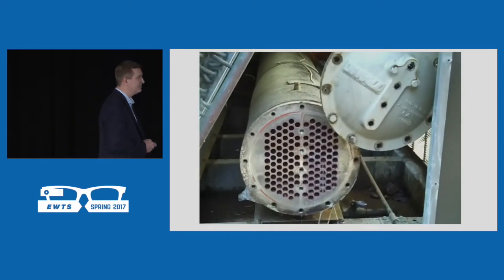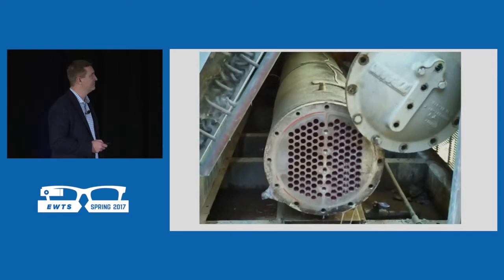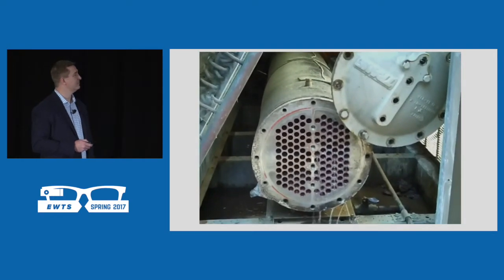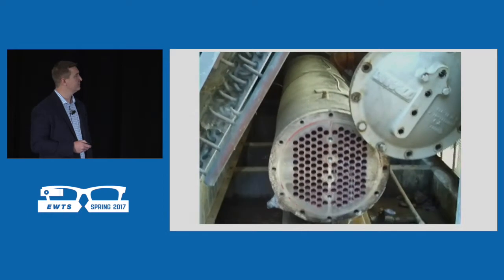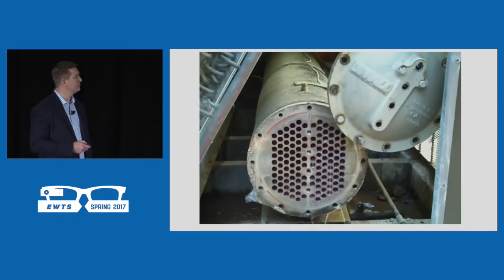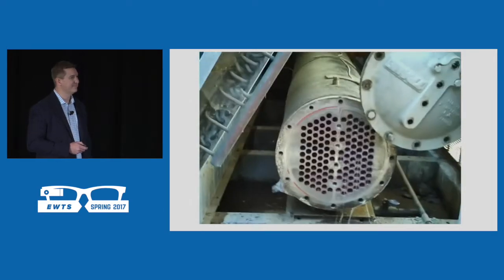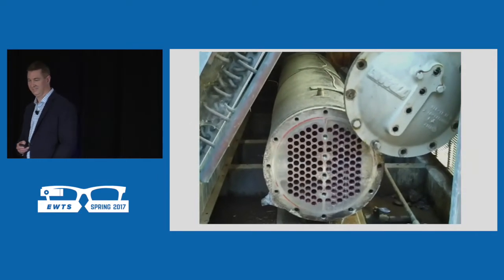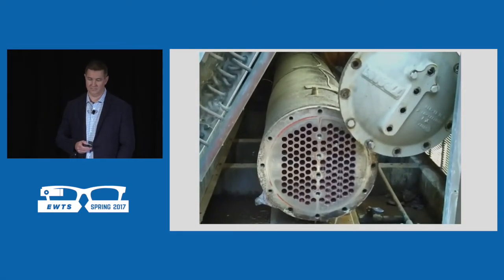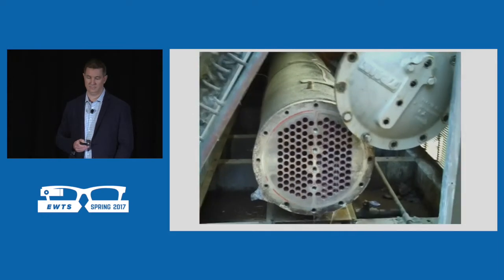Hey, this is Matt with Brady. It's March 8th. I'm at NC State, Sullivan 1, CGAF chiller. There's water in the suction line and the refrigerant side. We've got the barrel off here. Circuit 2, it's leaking on the refrigerant. This is the refrigerant tubing, and as you can tell with water coming out of it, pretty much we would condemn the barrel at this point. By the time you went through and capped off the ends, it would be hardly anything there to cool. Also, we found both compressors on circuit 2 shorted to ground with the megger. So between the two compressors and the barrel on the second circuit side, those would be the repairs. So we'll give a quote and let us know how we can help you. Thank you for choosing Brady.